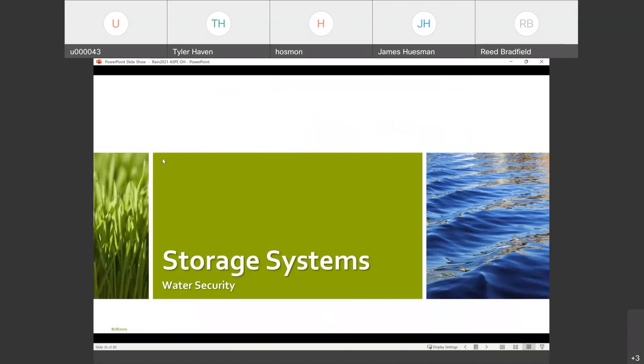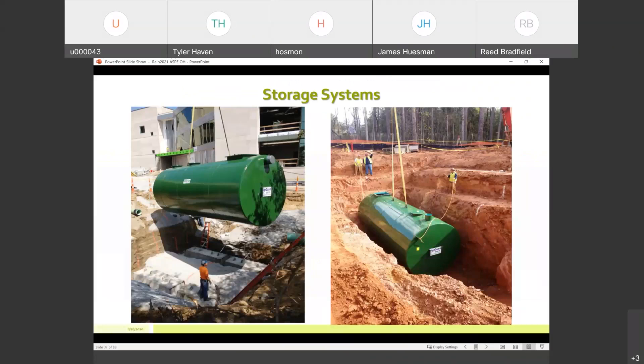Storage systems — as we talked about, storage is the most expensive but the most important part of any of these systems. Having secure storage, making sure there's no groundwater infiltration, making sure the system going in the ground is correct — because you have these huge buildings with an eighth-inch-per-foot fall needed to get that stormwater to that component. Sometimes these things get pretty deep in the ground, so you've got to be cognizant of real calculations, overburden, and depth of burial. It's super important to get the civil engineer involved right away so we know potential cuts and how deep these components might be if they're going underground.